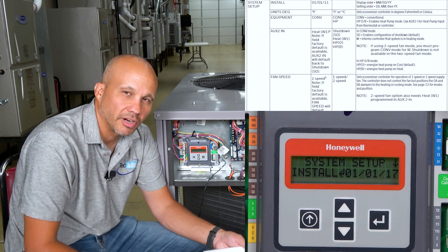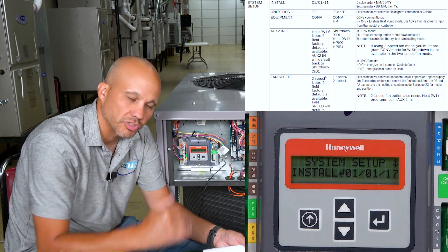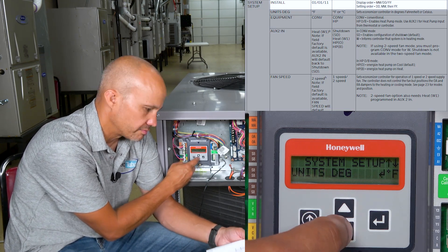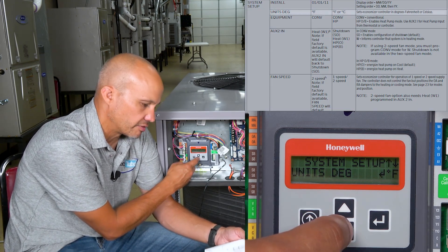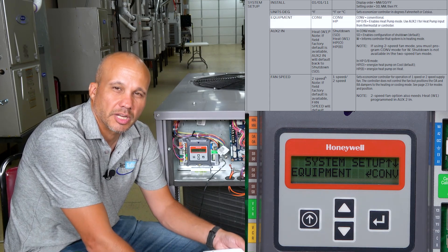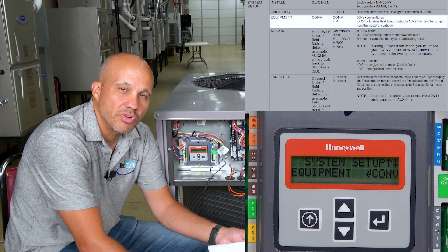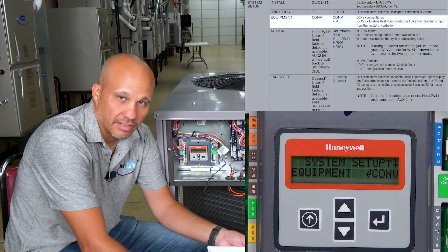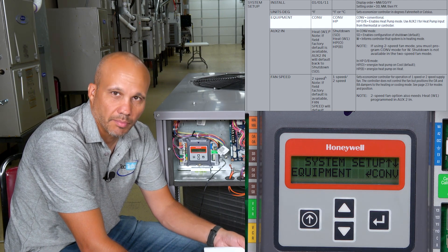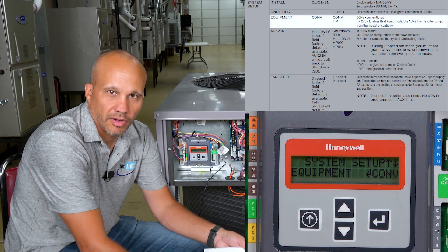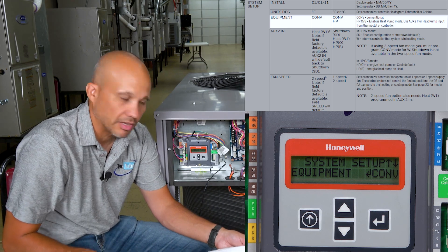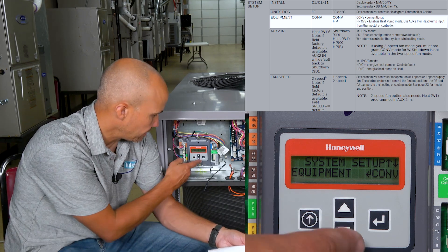The menu goes sequentially in order — we'll skip a few to save time. Install date is self-explanatory. Degrees Fahrenheit or Celsius is self-explanatory. Equipment: Conventional or Heat Pump. Conventional means everything that is not a heat pump — gas heat, electric heat, even a wood-fired pellet heater goes under conventional. Heat pumps are the only thing that goes under Heat Pump.